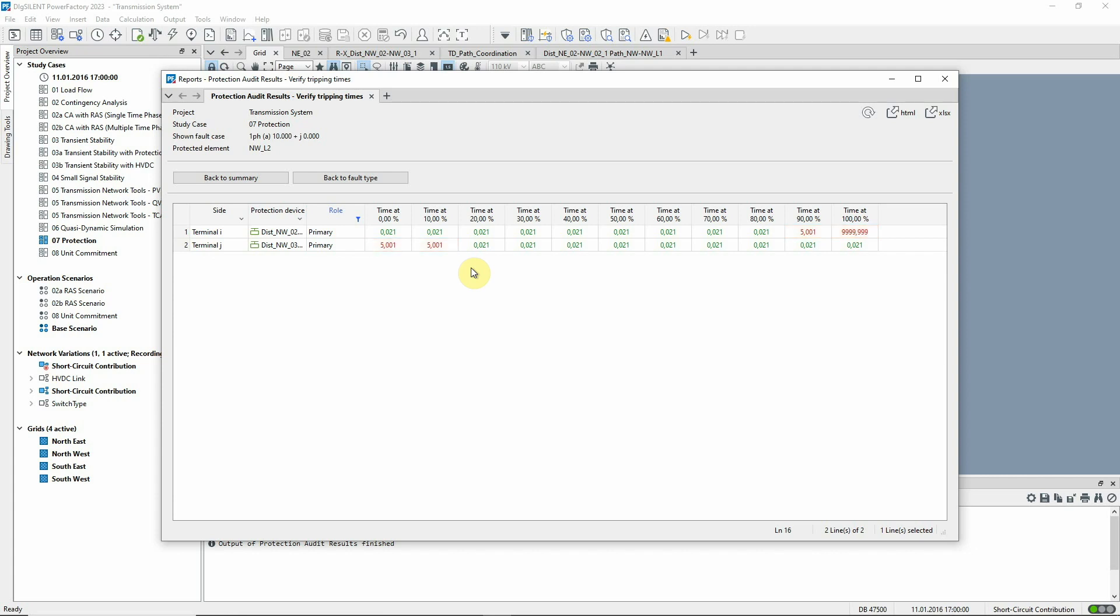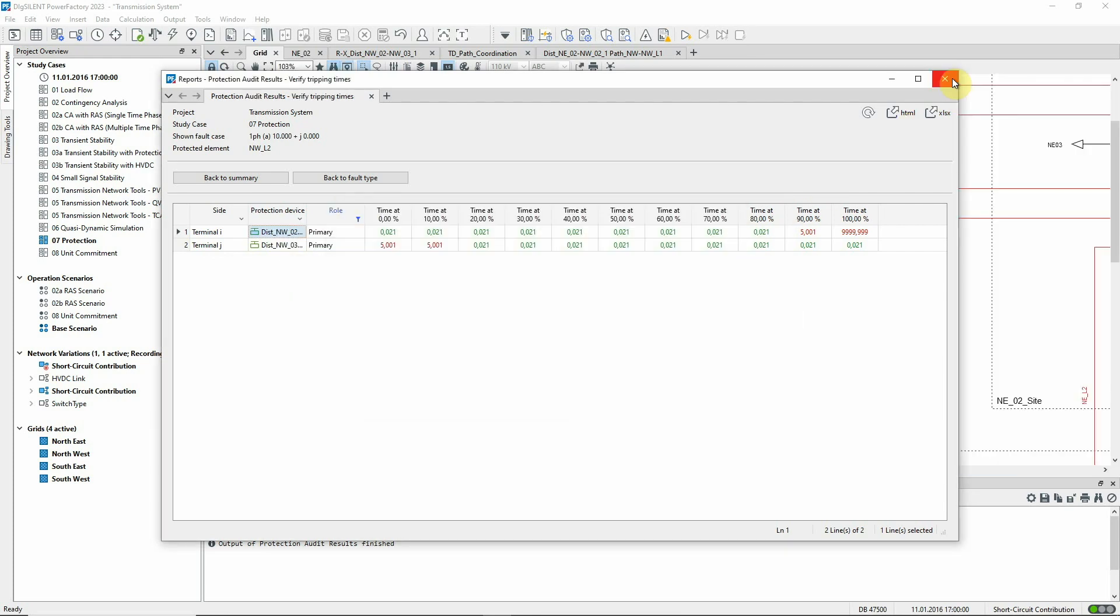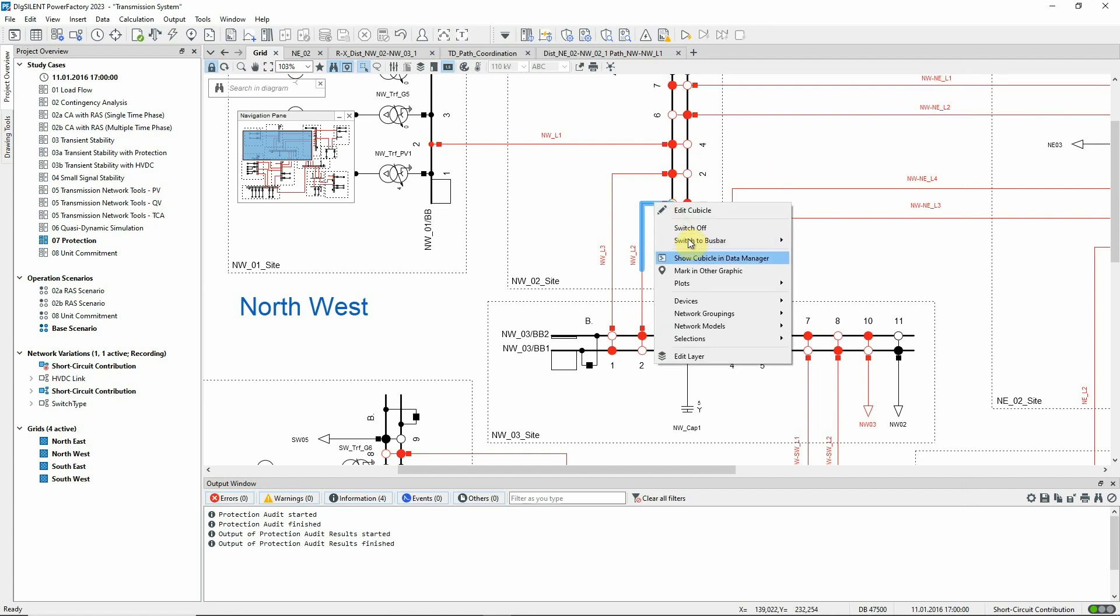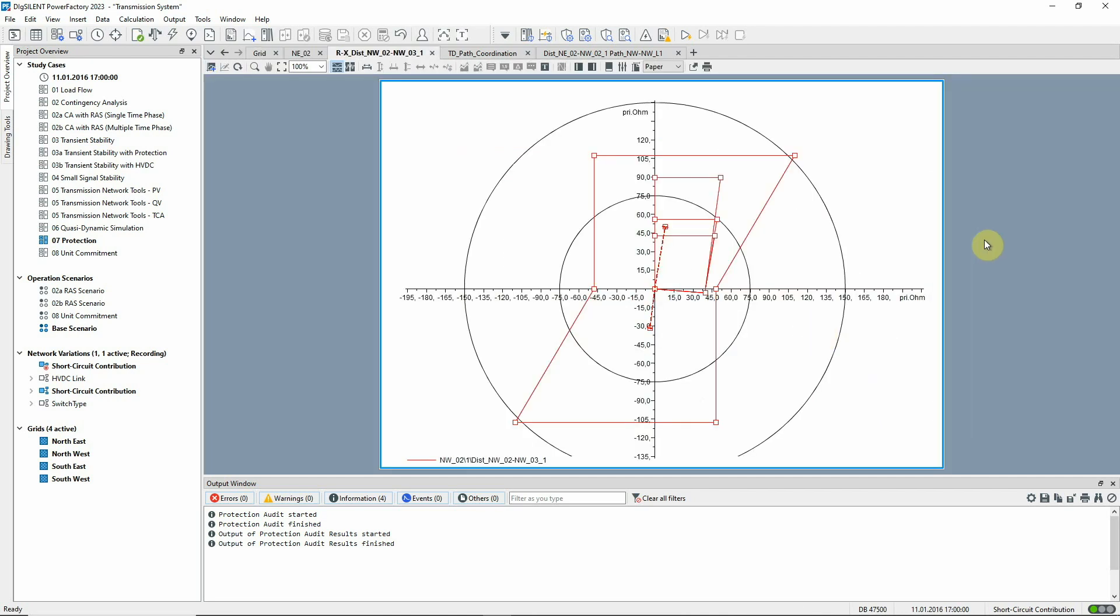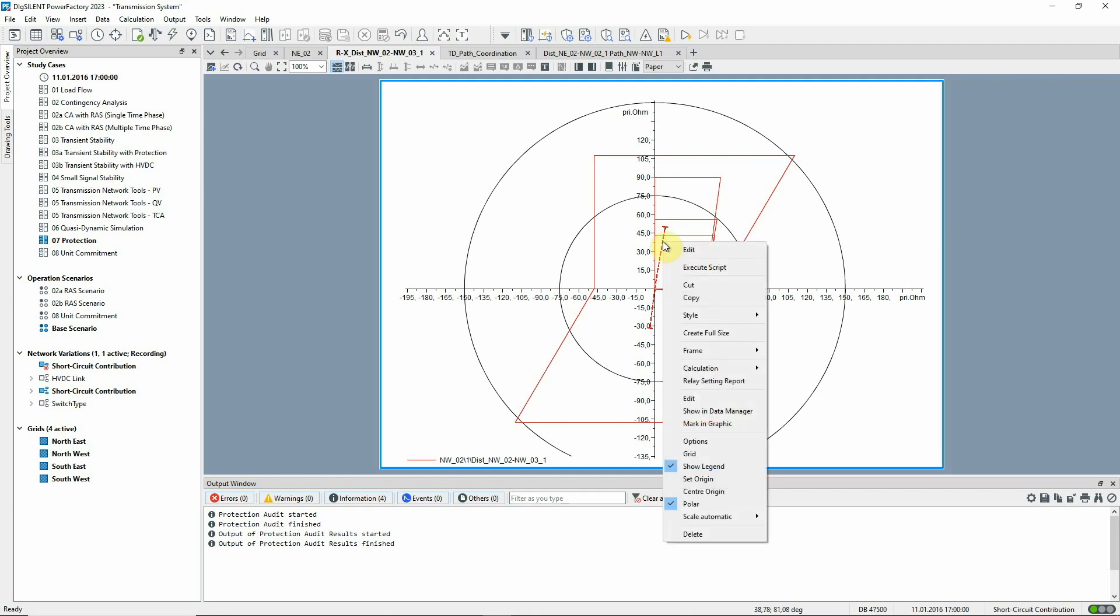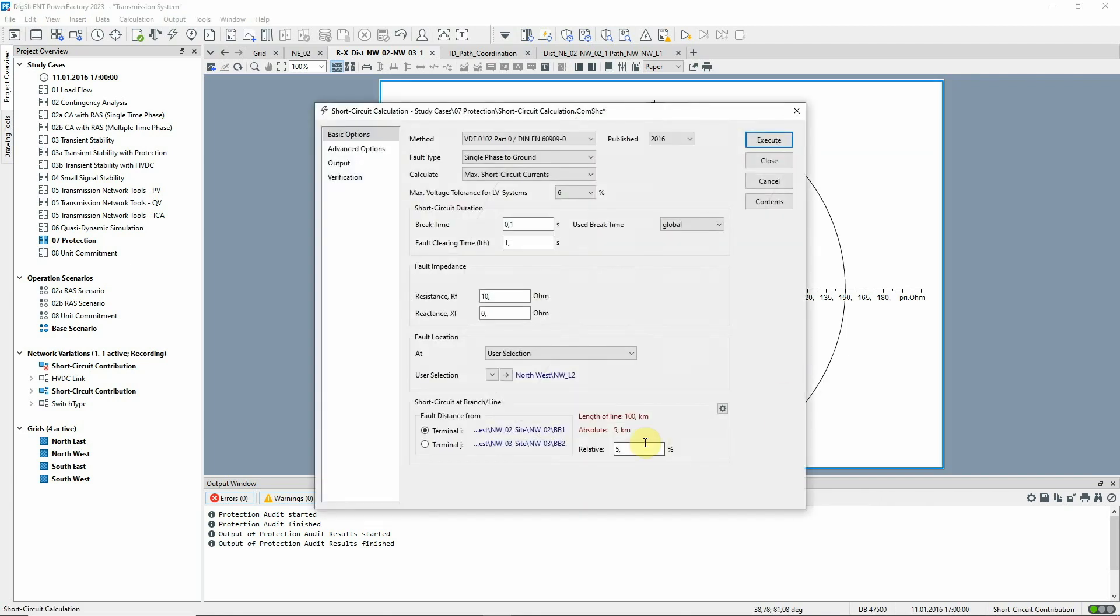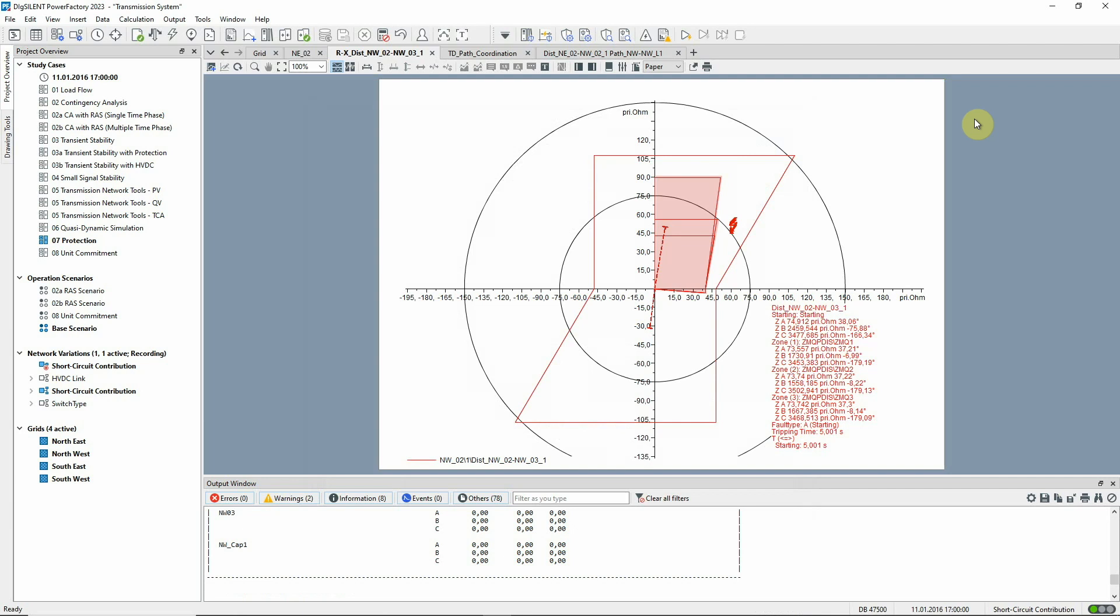We've identified a critical case and have to take a closer look at the network. Let's mark one device in the graphic and we can look at the relay's Rx plot. Let's calculate the same fault on the remote end of the relay. We can see in the Rx plot that the resistive zone reach is too short and the zone settings should be adapted.